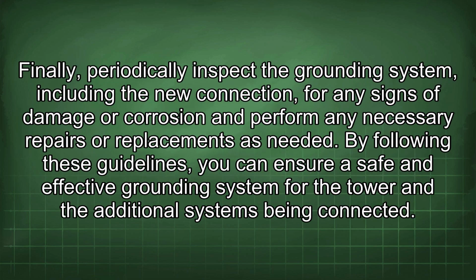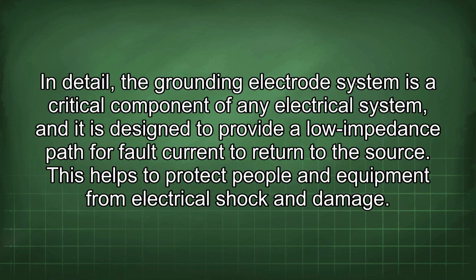Finally, periodically inspect the grounding system, including the new connection, for any signs of damage or corrosion and perform any necessary repairs or replacements as needed. By following these guidelines, you can ensure a safe and effective grounding system for the tower and the additional systems being connected. In detail, the grounding electrode system is a critical component of any electrical system, and it is designed to provide a low impedance path for fault current to return to the source. This helps to protect people and equipment from electrical shock and damage.